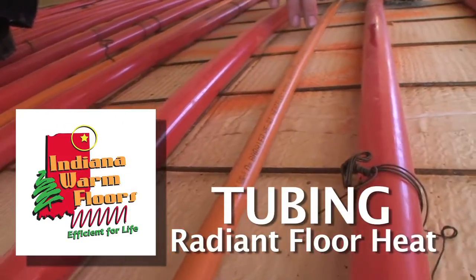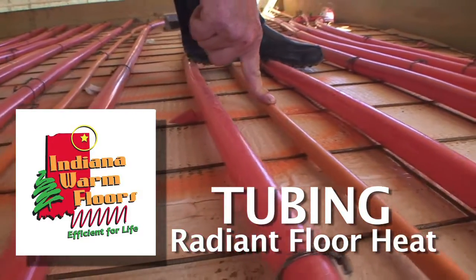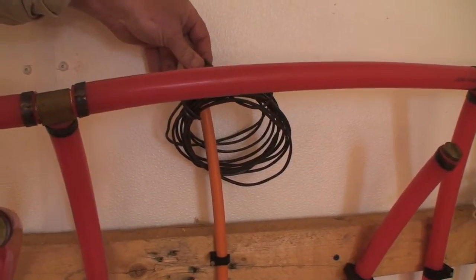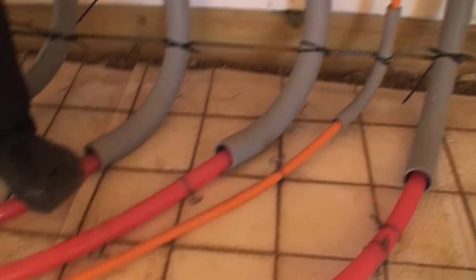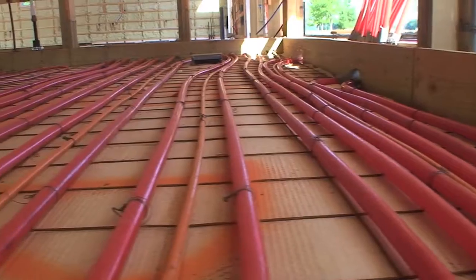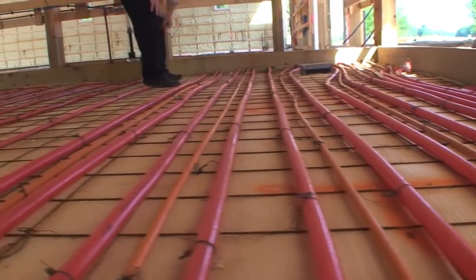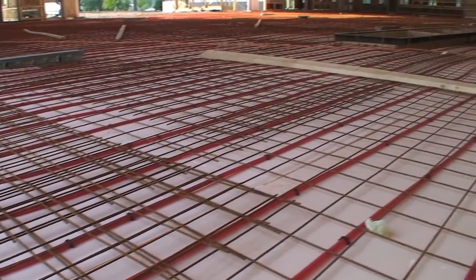This is PERT tubing from Oil Creek. We're using it on this application for a thermostat conduit going out to the large zones, so they're run in the slab as the crow flies, and it makes it a lot easier for us on installation. The red pipe here is an oxygen barrier PEX — crosslink polyethylene. This particular pipe is a Giacomini pipe out of Italy, supplied by Legend.